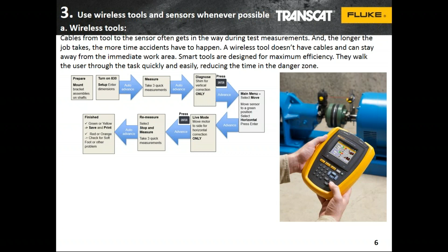So what we need to do first is find out what the problem with our machine is—the root cause. That's what vibration testers are designed to do: tell us not just that the bearings are bad, but that maybe we have misalignment or imbalance.